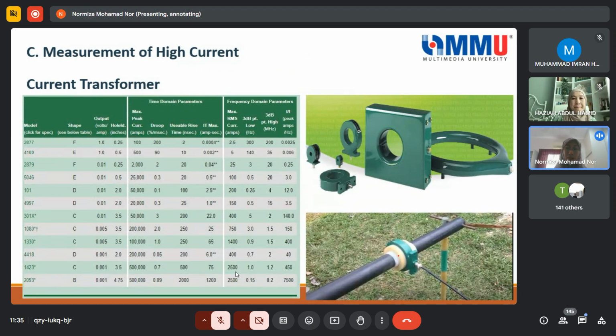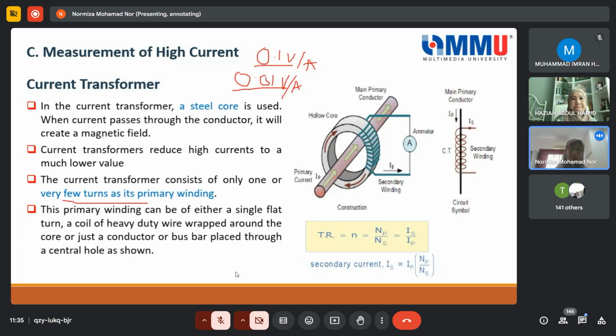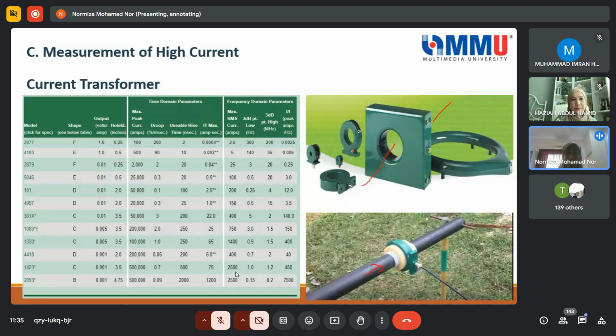So it also comes in different range. This is the one that we connect at MMU, where you can see here the black is the insulator, because we do not want to have flashover from this metal current transformer to the cable. You have to put the current cable through the hole here. In some cases it can cause flashover between this metal core and the cable. So for that reason, we have this hollow epoxy insulator, and then we put the current transformer, and still the current can induce and produce the output voltage.